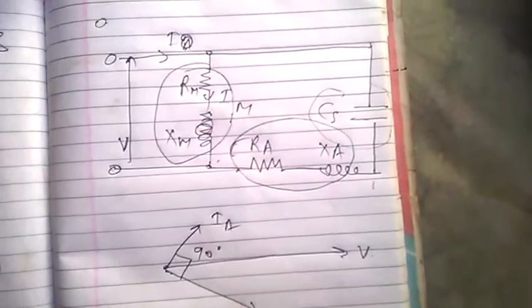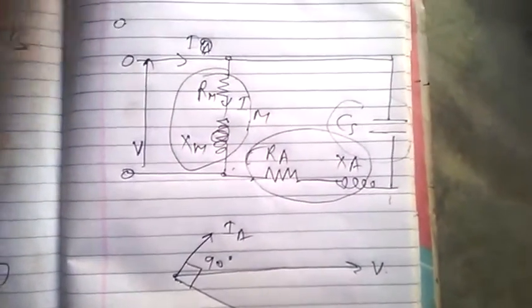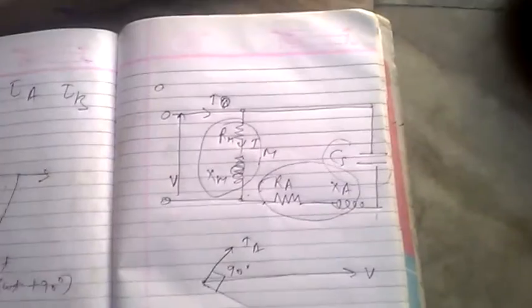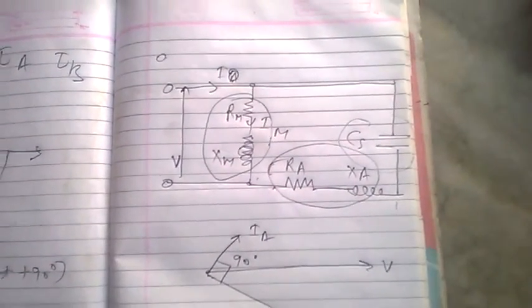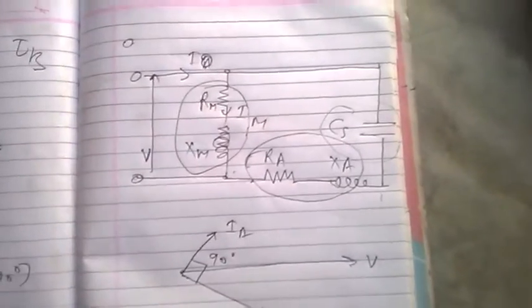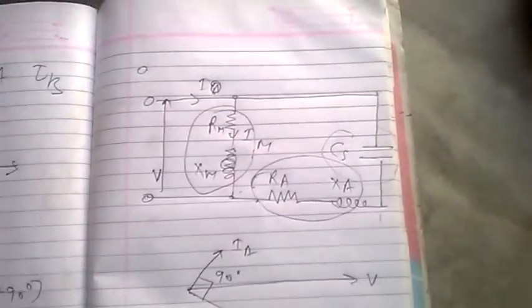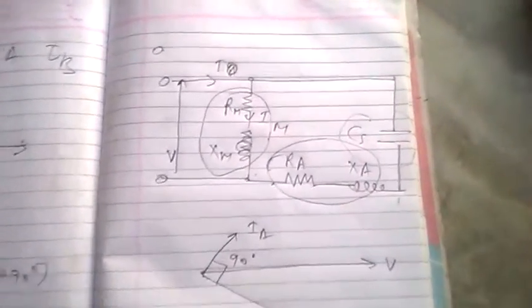The capacitor is permanently connected in circuit, both at starting and running conditions. A permanent split capacitor motor is also called a single value capacitor motor. Consequently it produces uniform torque. The motor is therefore less noisy during operation. So that's the full support of this.